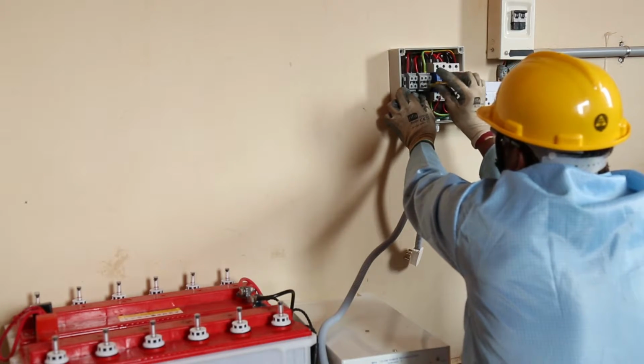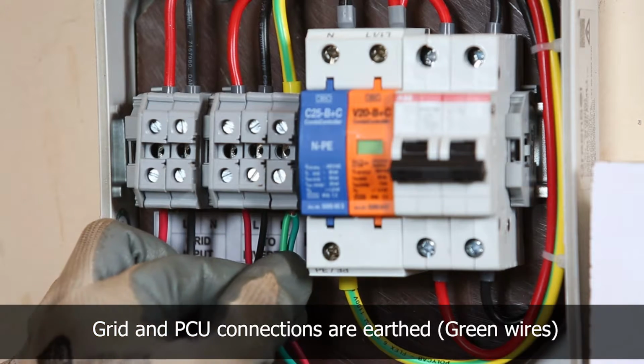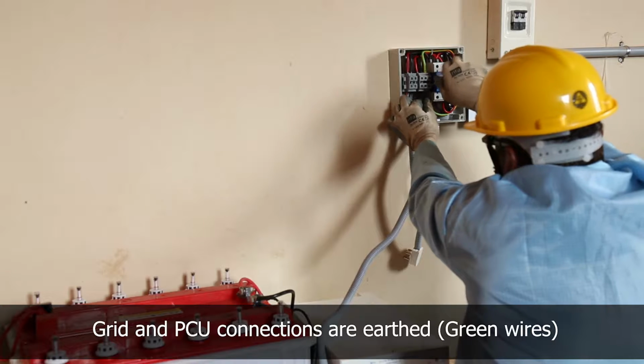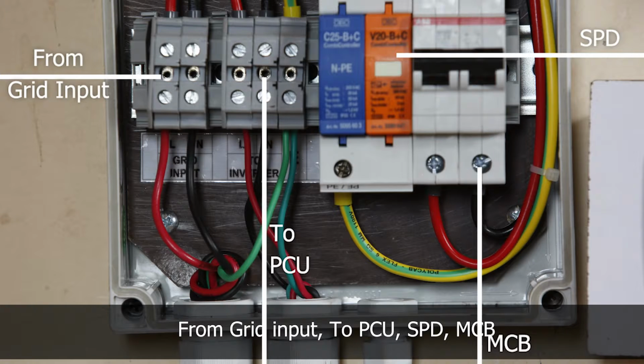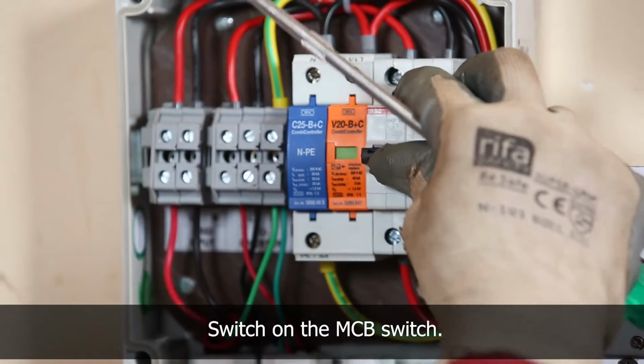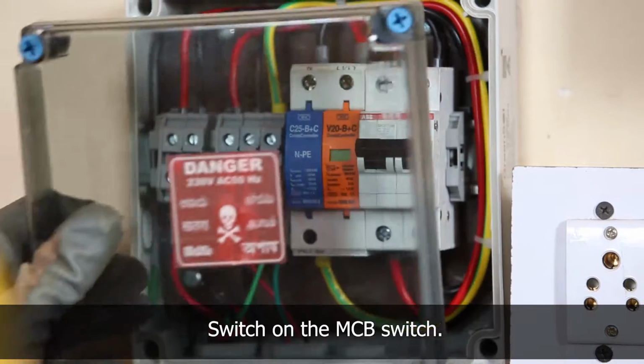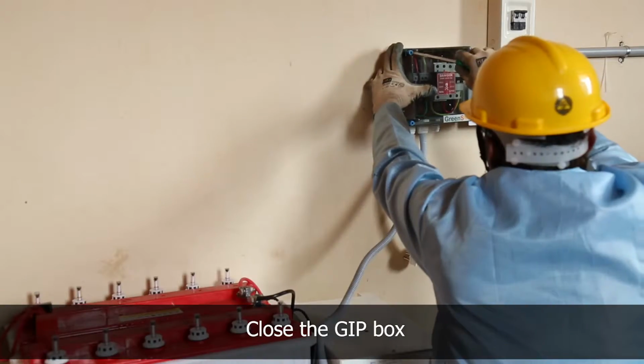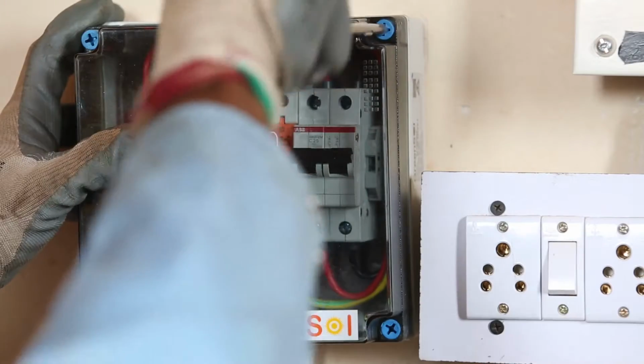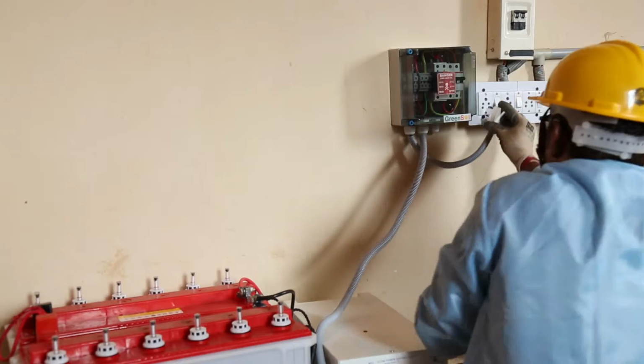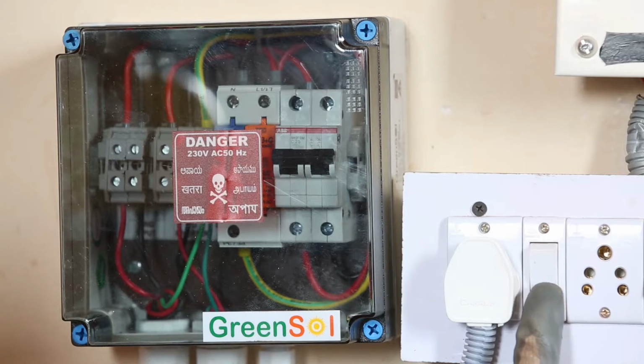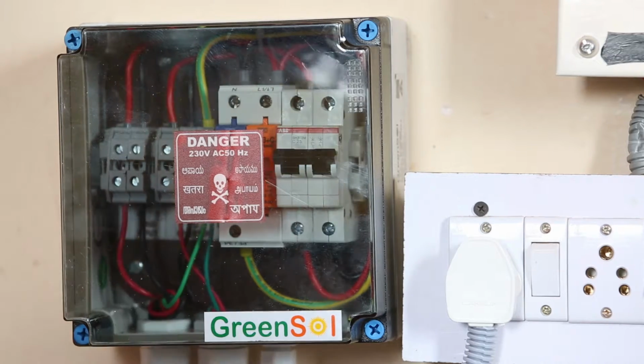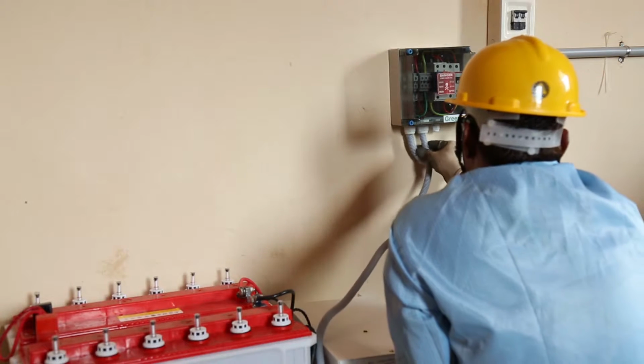Connect the earthing wires of the grid and power conditioning unit together to the earthing terminal of the grid input protection box. The grid input protection box connection is complete. Now, turn on the miniature circuit breaker switch and cover the grid input protection box. Connect the plug from the grid input terminal of the grid input protection box to the grid.